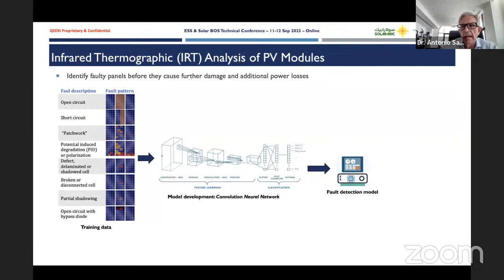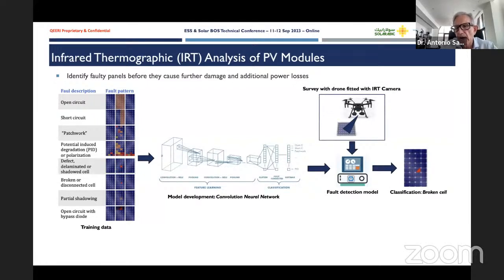And then at runtime, you feed pictures of the panels of your PV plant. You can collect these pictures with a drone fitted with a thermographic camera, especially in the case of a big plant. You don't want to go there with a handheld device, it takes too long. And you feed it to the model, and you get a response as to whether the picture is indicative of a fault or not.